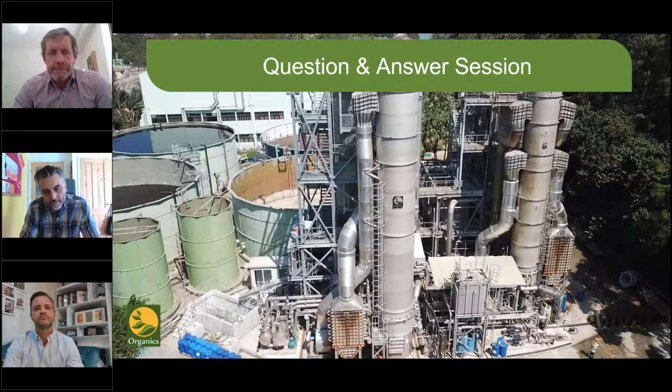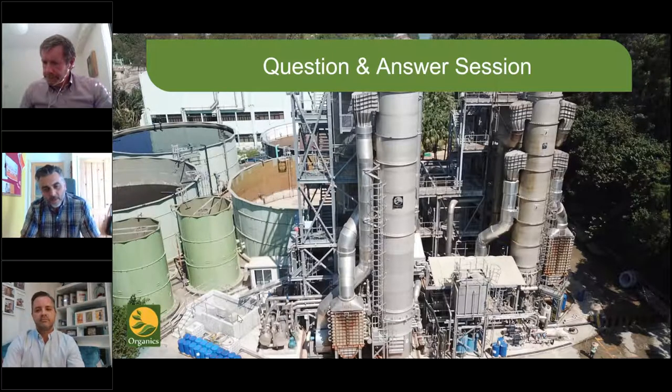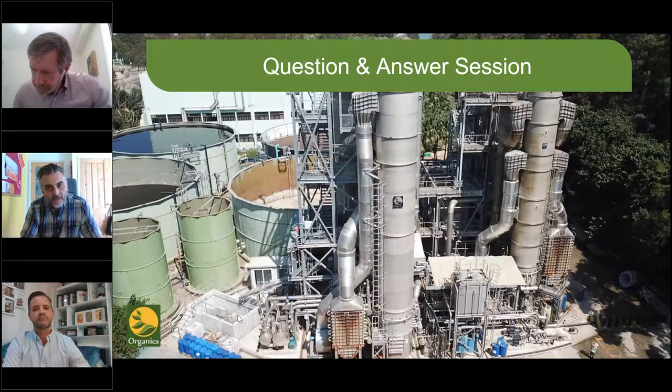And we have got three or four things that we use. First of all, we've got two places where we can introduce the ammonia. We can introduce it as primary air or as secondary air. We can then introduce the combustion gas either above or below the ammoniated air. And then we've also got careful temperature control of the combustion air that we allow in on top of the ammoniated air. And finally, we use exhaust gas recirculation, so that we can use the low oxygen exhaust gas, bring it back in at the bottom as a cooling gas to allow us to bring in cooling gas without additional oxygen. So we have three or four methods that we tune up on site when we have to pass our emissions test during commissioning, usually with the local government authority.